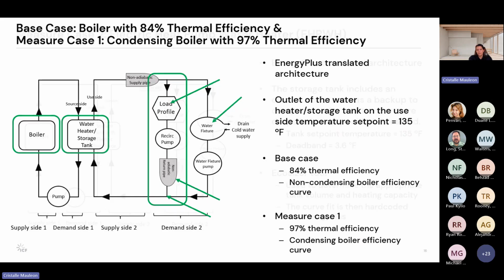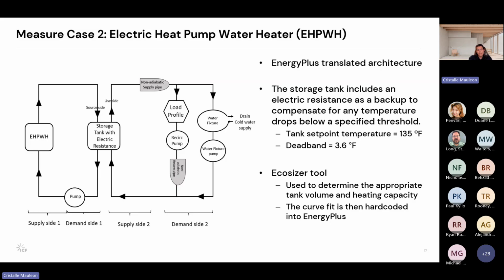but that's how the sizing is done for that one. For the electric heat pump, if you go into EcoSizer and you put in a certain number of multifamily apartments with a certain temperature set point and number of people per apartment, it gives you a curve that you can adjust the storage tank volume and the electric heat pump capacity. And so we put that storage tank versus capacity into EnergyPlus, and then we again let it size the storage tank and the electric heat pump capacity for us. And we're using the same flow rates and the same recirculation load as we were before. So again, it's really just the difference in groundwater temperature.